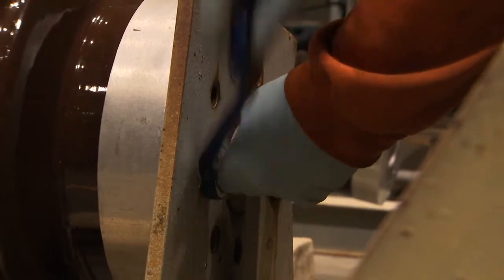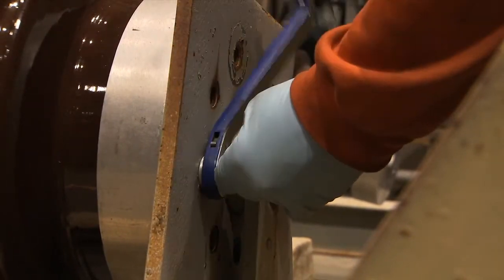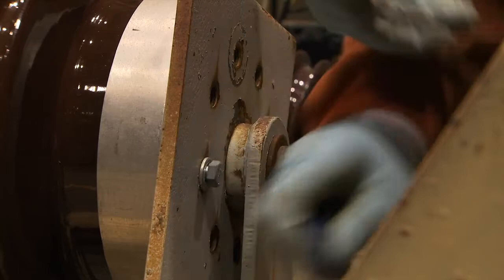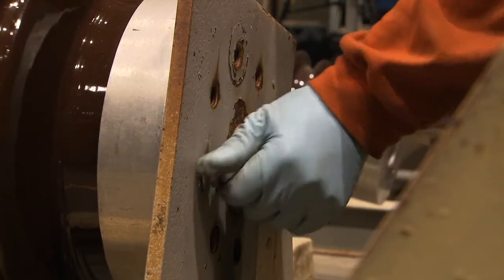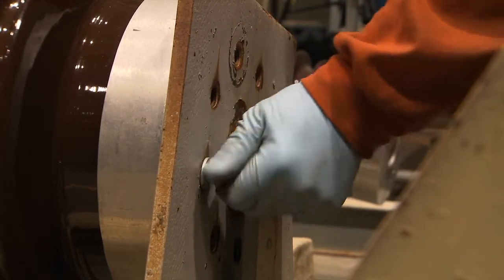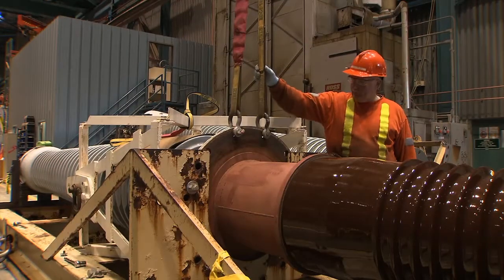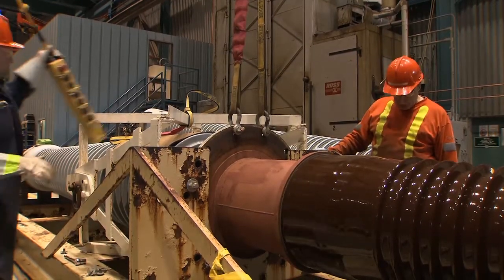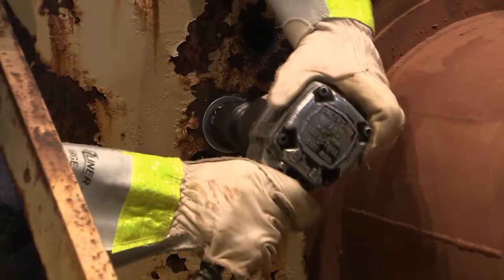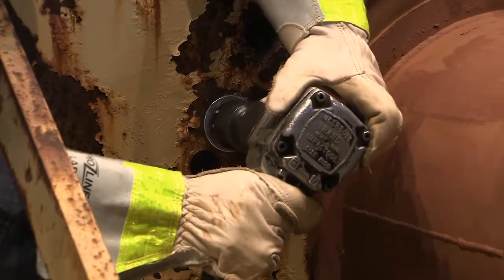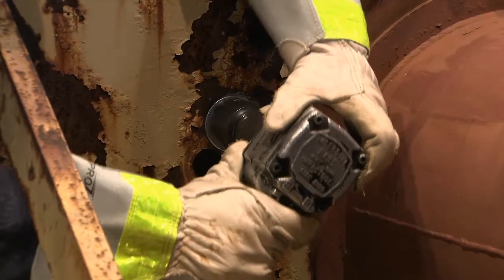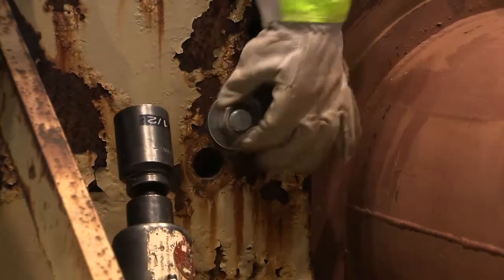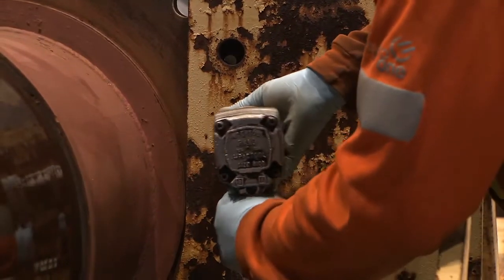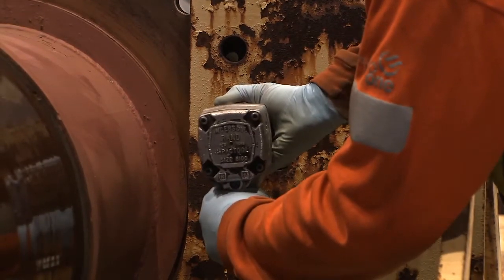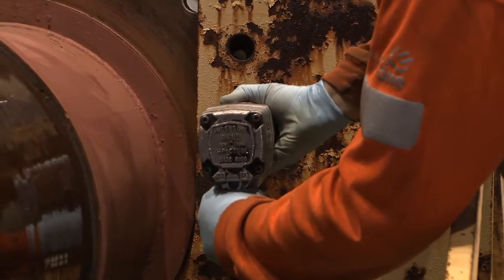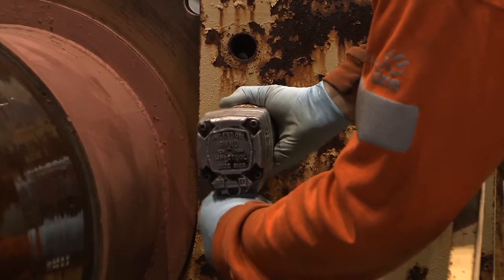Use a ratchet wrench of the appropriate size to loosen all of the bolts. Once loosened, manually remove them from the flange. There may also be some bolts that are still in place attaching the mounting flange to the transport carrier. By raising the bushing incrementally, using the remote control for the hoist hook, the weight on the bolts still remaining can now be relieved enough to remove them.